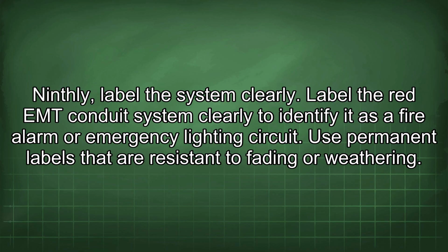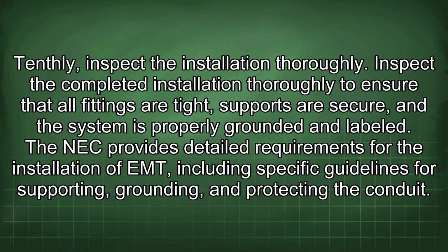Label the red EMT conduit system clearly to identify it as a fire alarm or emergency lighting circuit. Use permanent labels that are resistant to fading or weathering. Tenthly, inspect the installation thoroughly. Inspect the completed installation thoroughly to ensure that all fittings are tight, supports are secure, and the system is properly grounded and labeled.